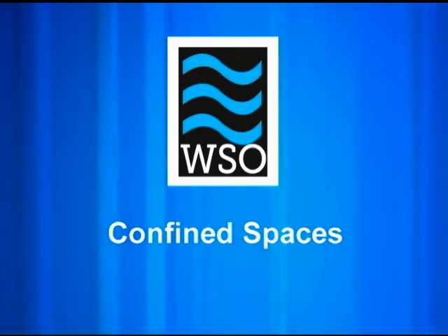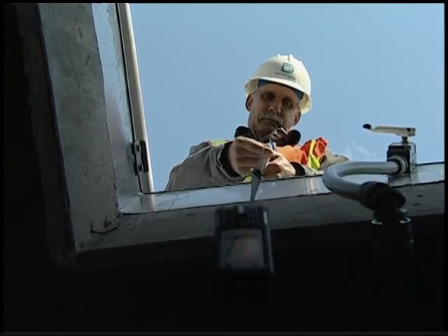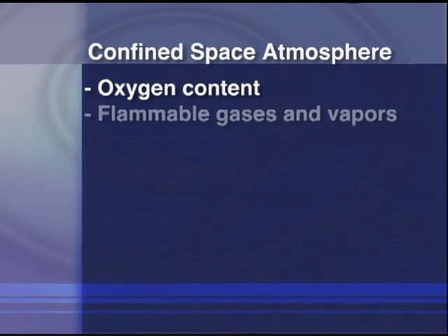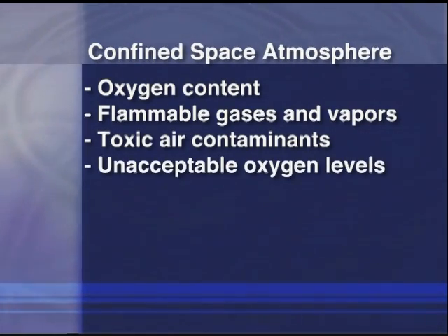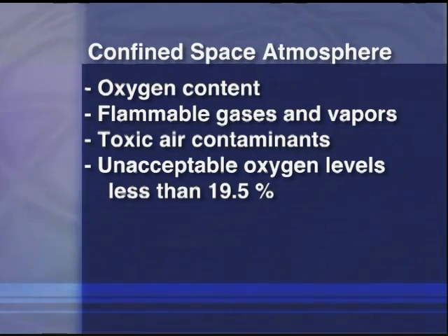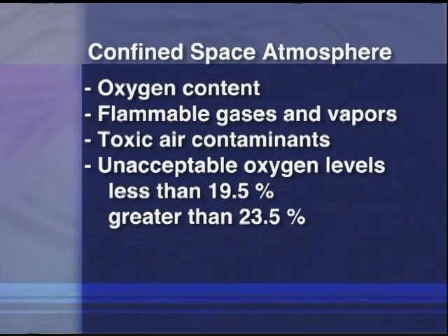The internal atmosphere must be tested with calibrated instruments that will determine oxygen content, flammable gases and vapors, and potential toxic air contaminants. Atmospheric conditions are considered unacceptable if oxygen levels are less than 19.5% or greater than 23.5%.